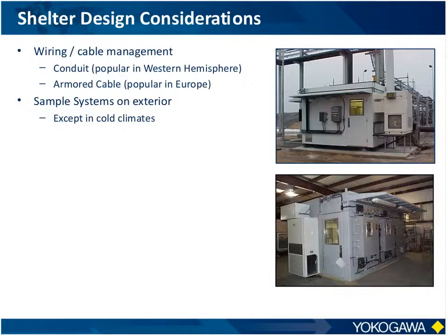Sample systems, again, help get the sample to the right temperature, pressure, and flow. Those tend to be mounted on the exterior - you can see that in the bottom picture, those big boxes mounted along the outside. This makes it a lot easier to get access, and also keeps the bulk of the sample on the outside in case of a leak.